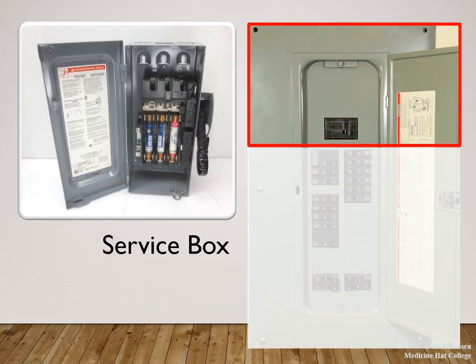Our service box, once again, needs to have two things. It needs to have overcurrent protection and it needs to have a form of disconnect. So it's the top part of the panel. Or we could also use something like a fused disconnect in order to facilitate the same purpose.